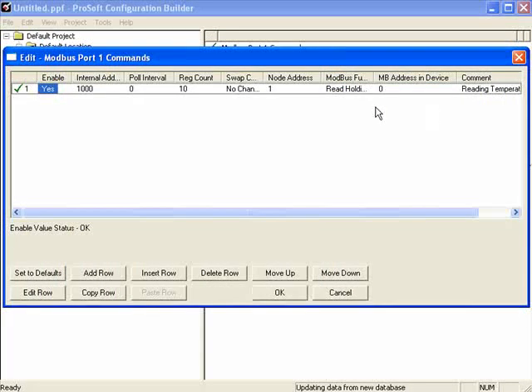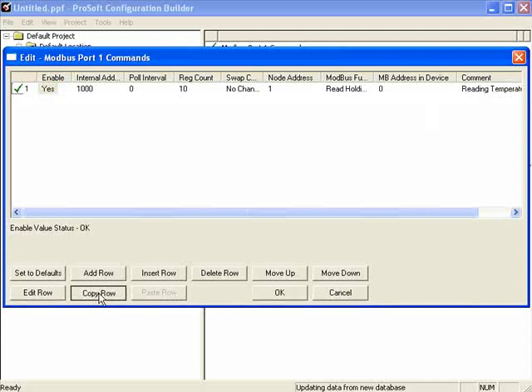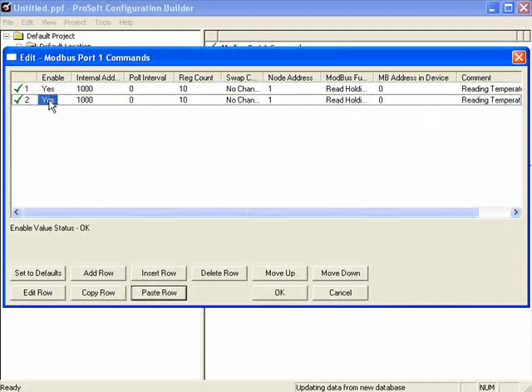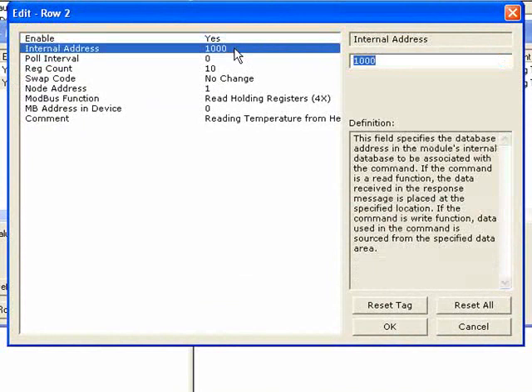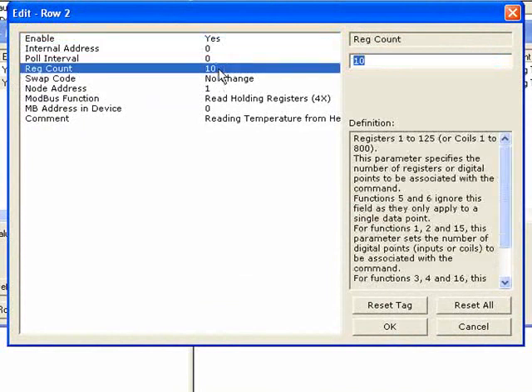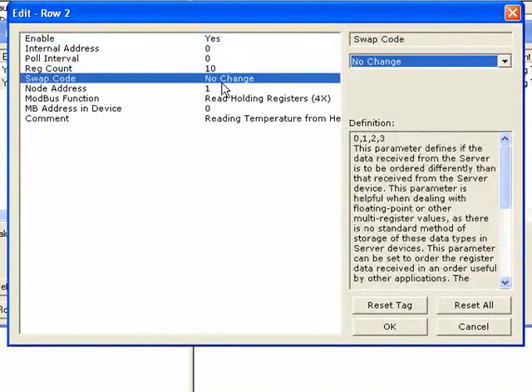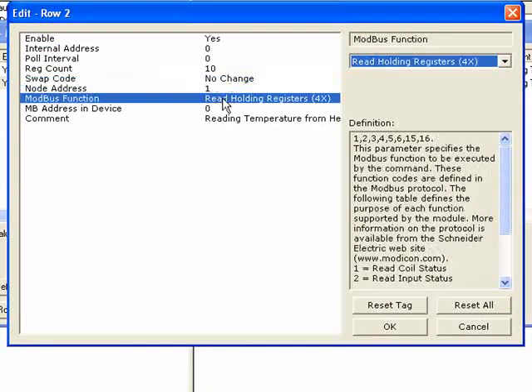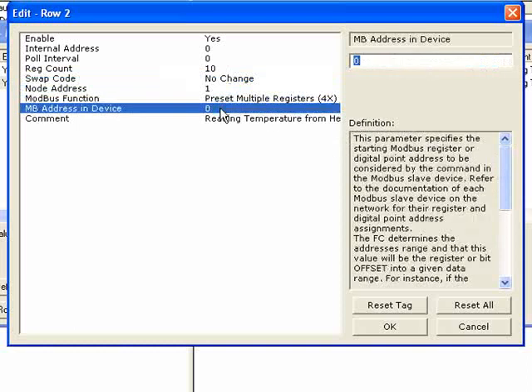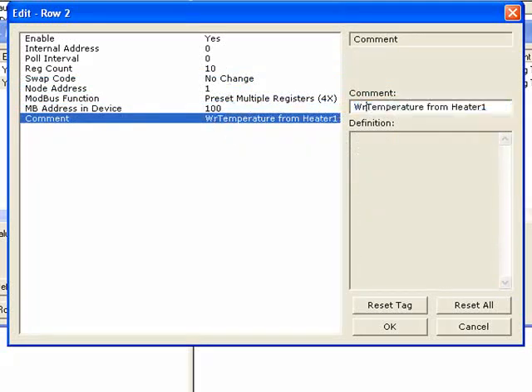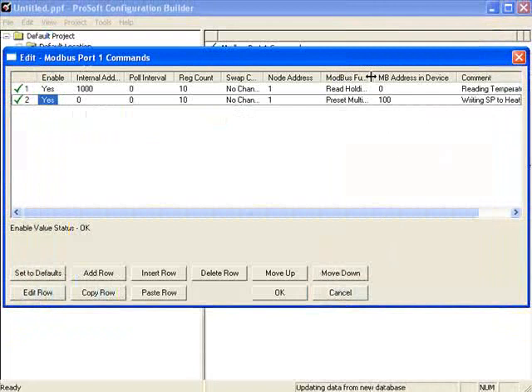I can click the Copy Row button — it's handy so you don't have to recreate every command. Since I'm going to the same node, I can just change a few parameters. I'll change the internal address to 0 because it's going to be a write command going to the write address. I'll leave the register count at 10 and change the Modbus function code to Preset Multiple Holding Registers. I'll change the address in device to 100, give it a different description, and click OK. Now we have our two commands going to node number one.